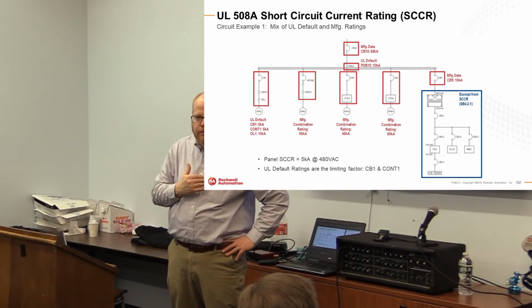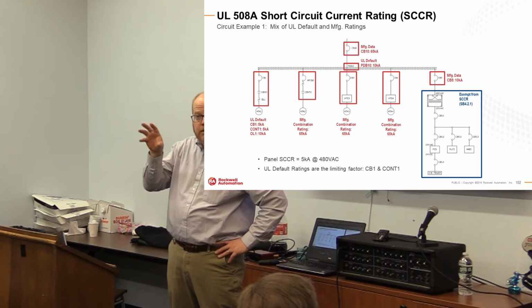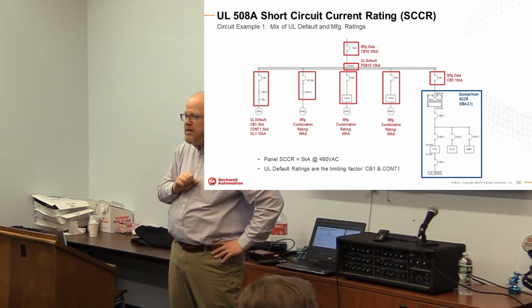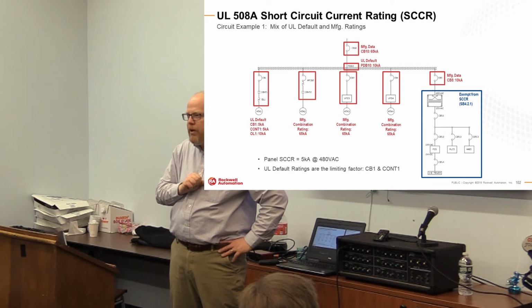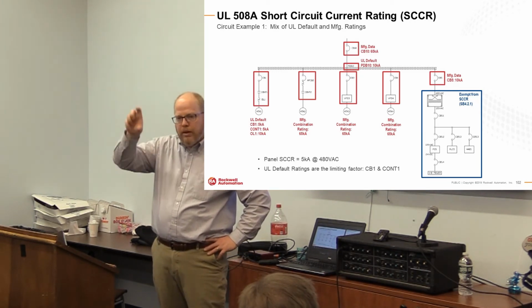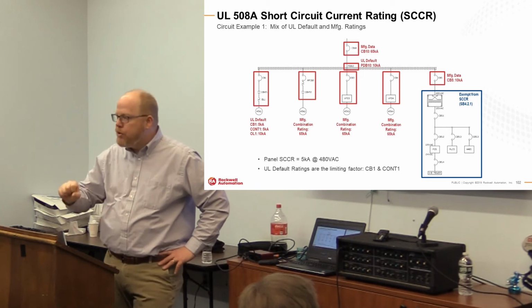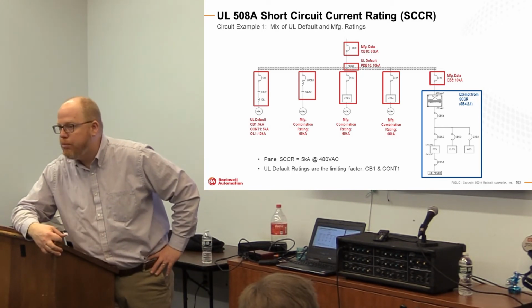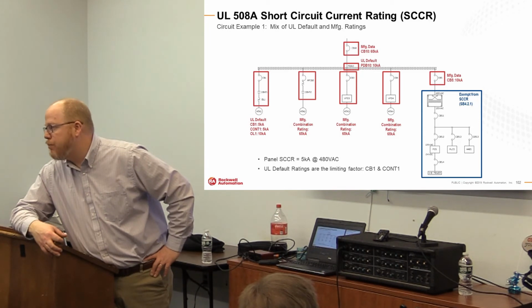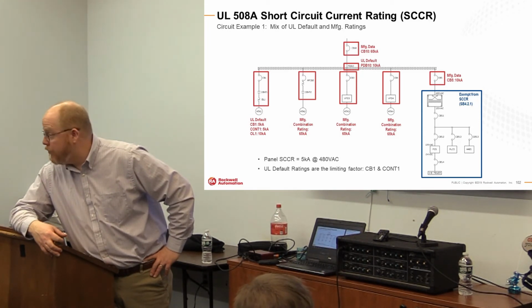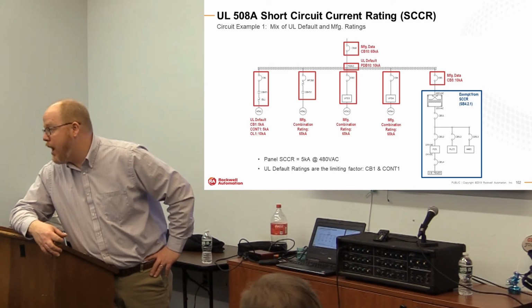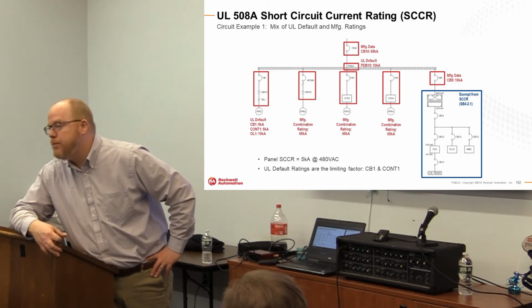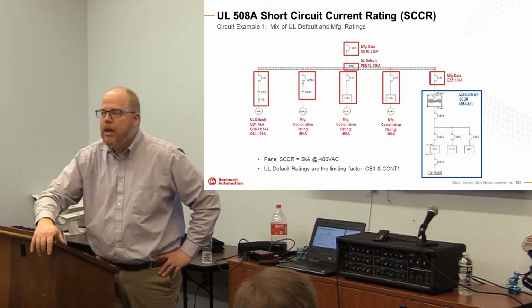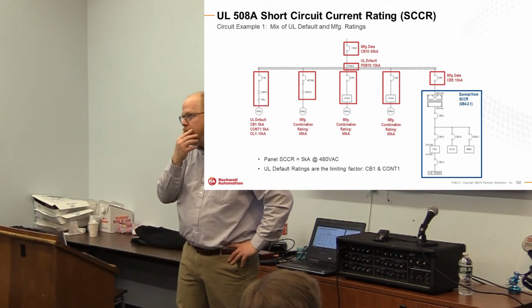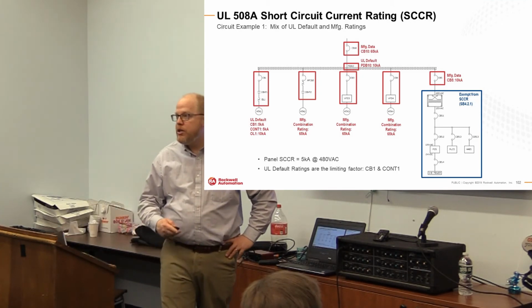The other way to get around it that I found is real helpful for optimizing not only panel space but cost is the multi-tap lugs that go on breakers. Have you started using these? They're handy because they're one less component on a backplate. But number two, if they're a UL listed accessory to the breaker, they carry the same rating as that breaker. So that's helpful. That's one very common pitfall around feeder power distribution that I see messes up SCCR. Again, we have them, our competitors have them, but I wanted to share that. Yes, sir.